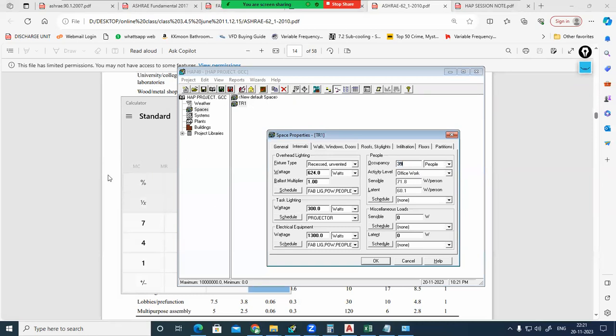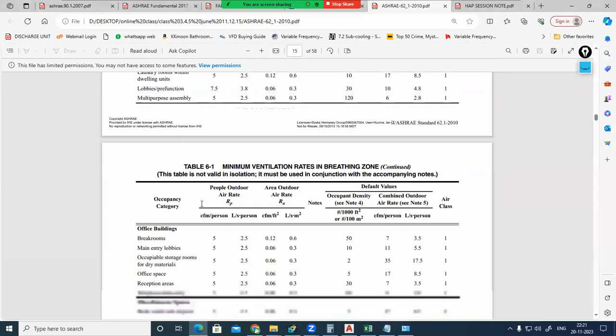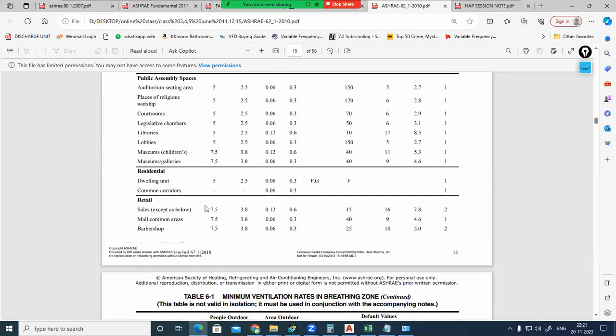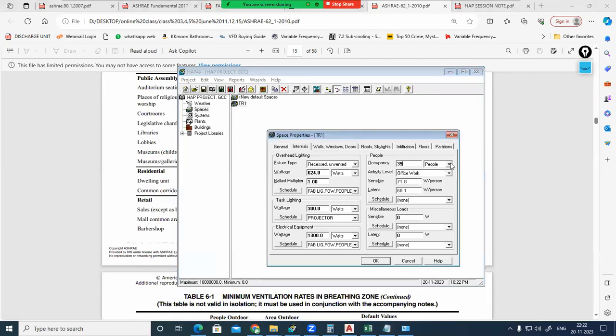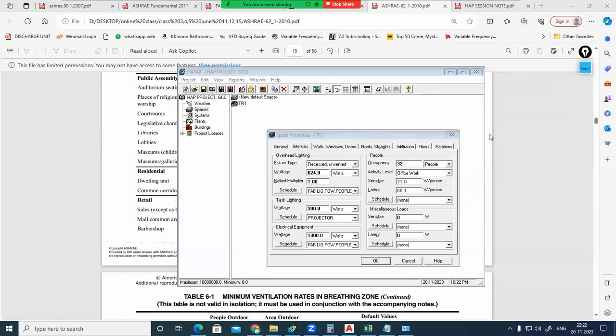So that's why, when you are designing a sales area, hotel, motel, and so on, this value we can provide. Mall common area, 40 people. For each person we need 2.5 meter square. So select 2.5 meter square. Then you can change that into people, 31.1. You can round that to 32 and assign it. I don't want to do the calculation here, but the calculation the software is following in the background is similar. Anyhow, if you have a furniture layout, go through that.